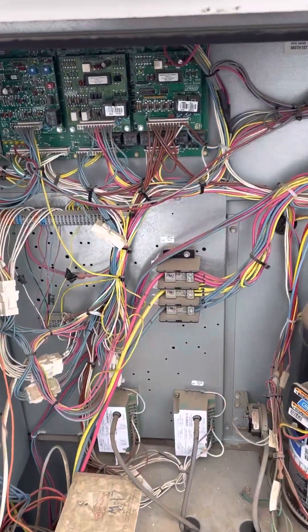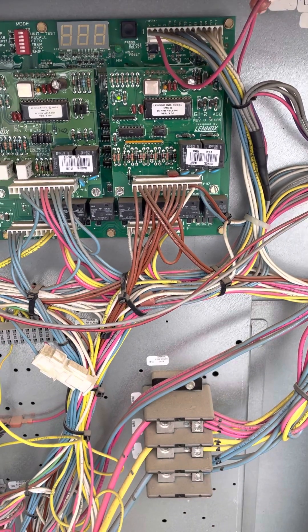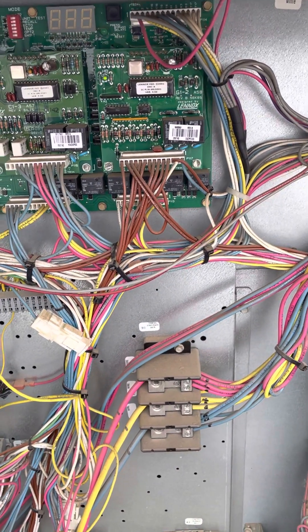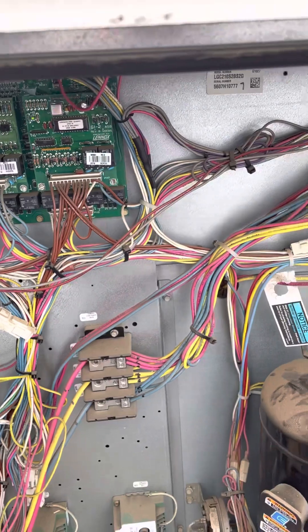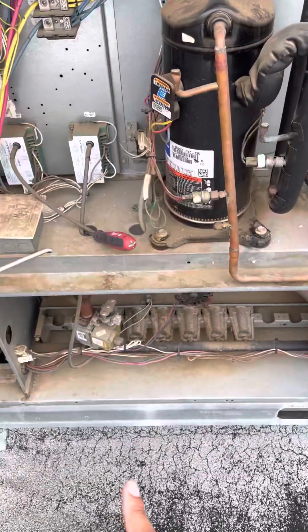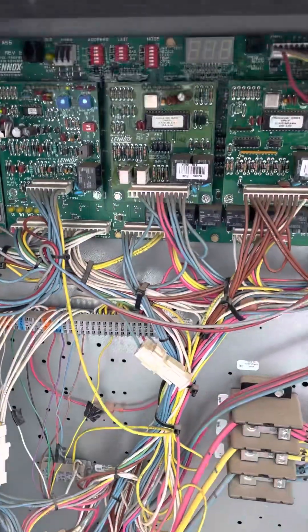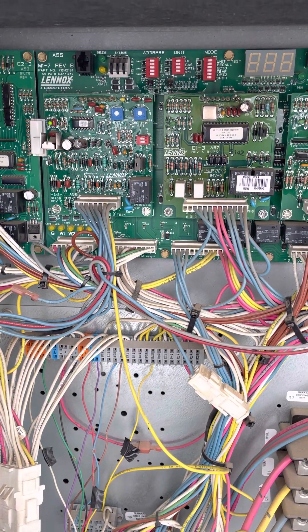In today's video I'm going to show you how to put these Lennox units in test mode. If you didn't know, there is a way that you can actually put these systems into test and you can test first stage cooling, second stage cooling, first stage heating, and second stage heating. The board in this unit is the M1-7 board.